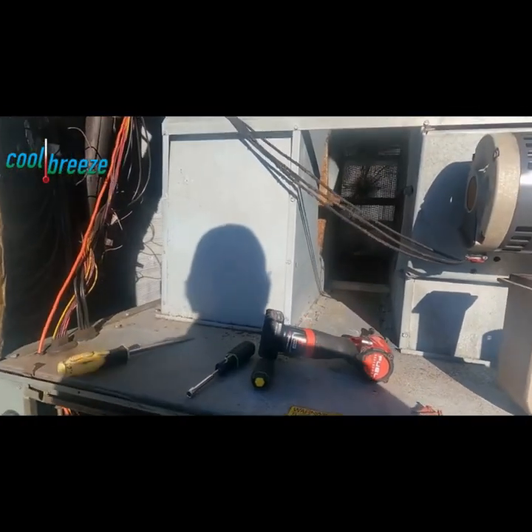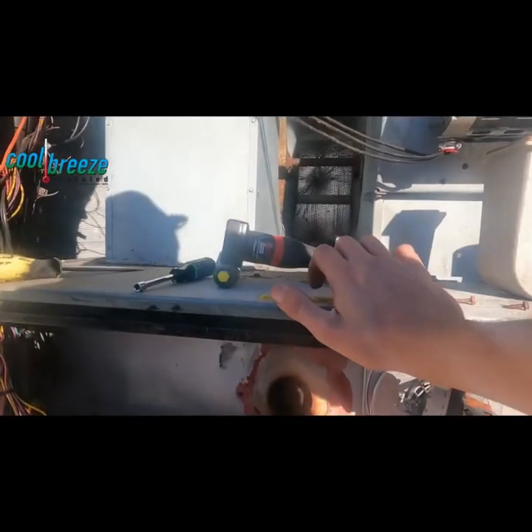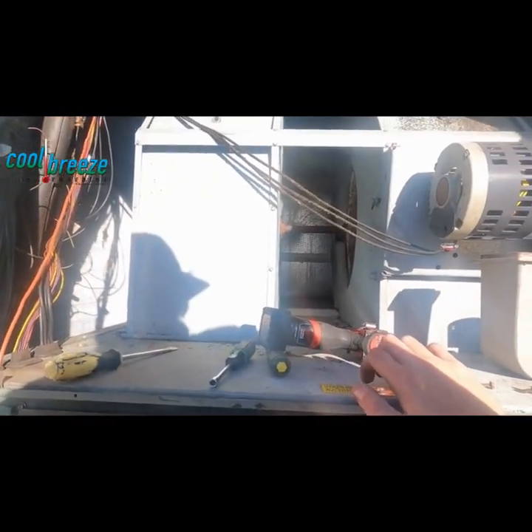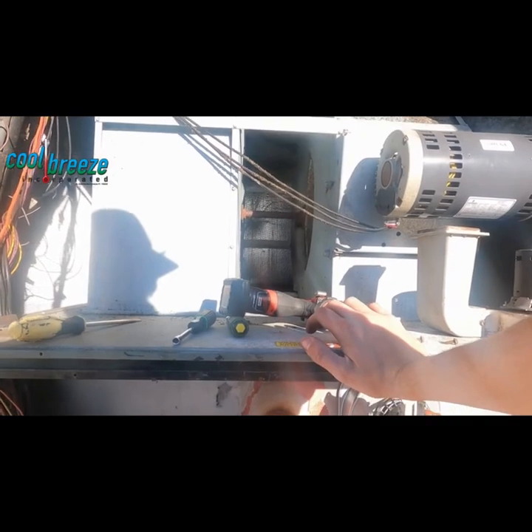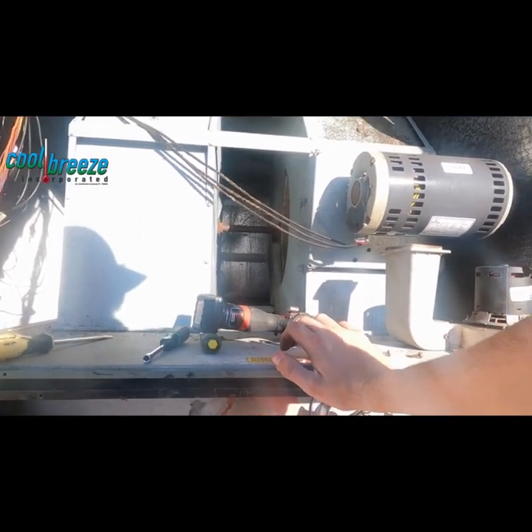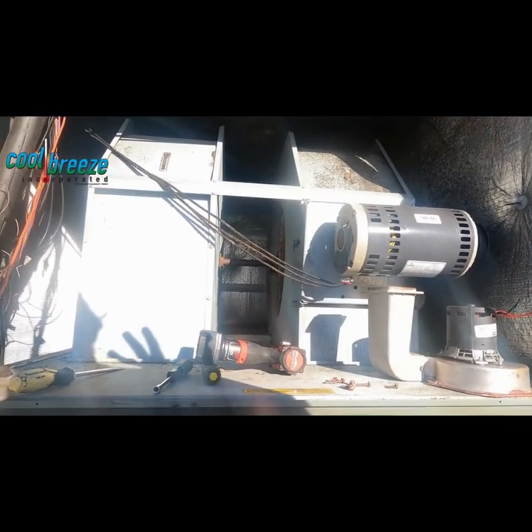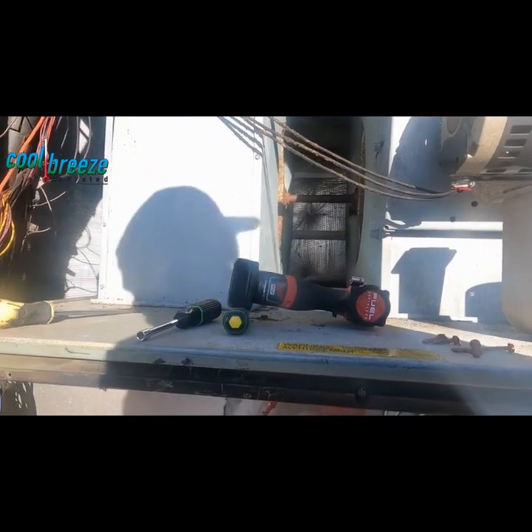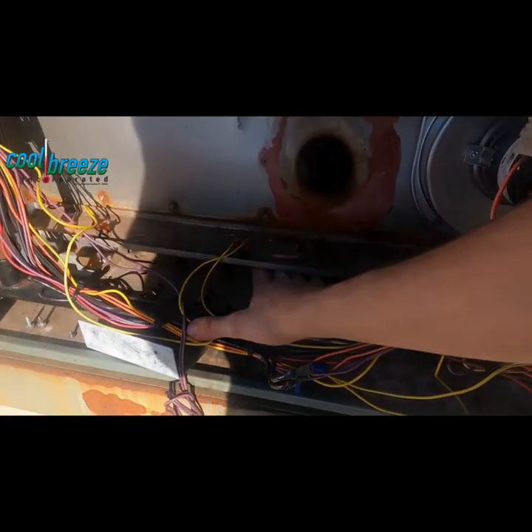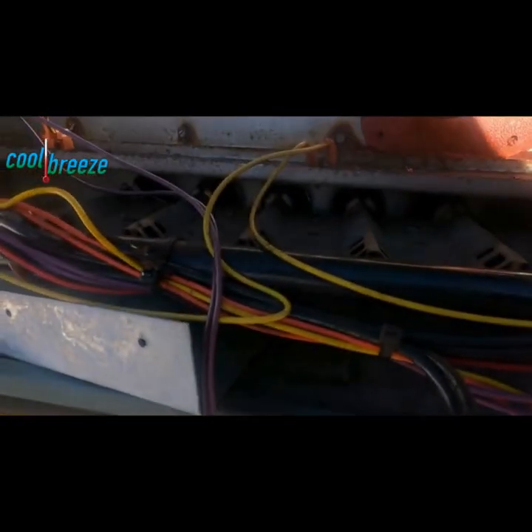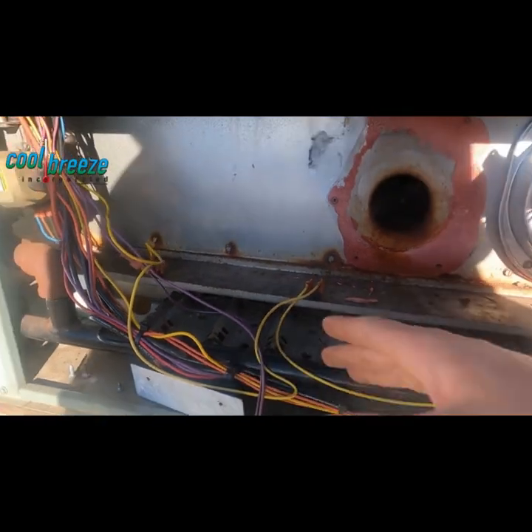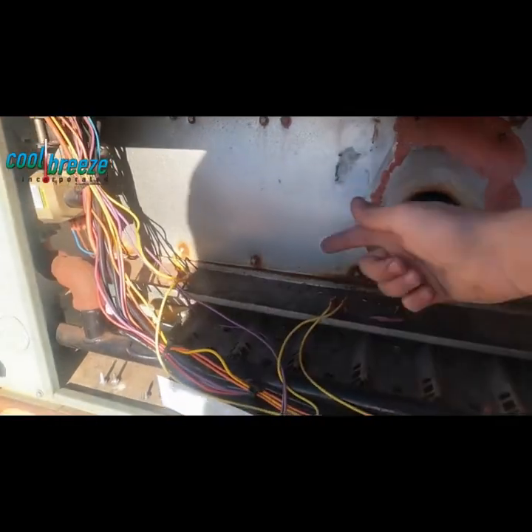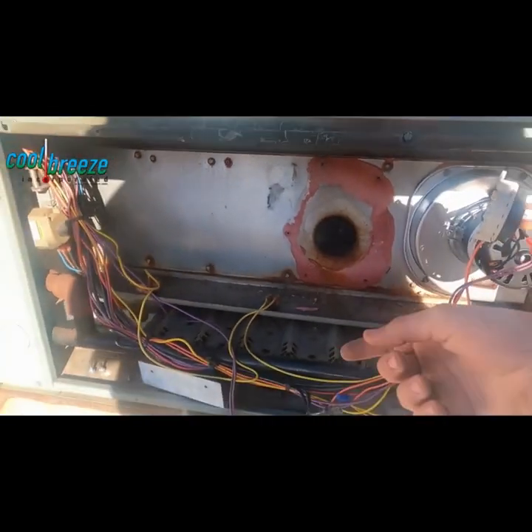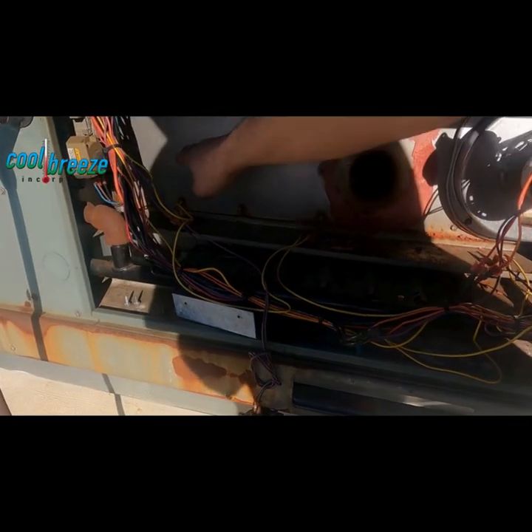Majority of the time, if you have a crack in the heat exchanger, if it's a good enough crack, you'll end up getting a rollout, which is where the flame comes out of the heat exchanger. These little tubes right here, that's the heat exchanger. So the gas is going in there, going through these tubes back and forth, back and forth, and then it comes out right here into this compartment.